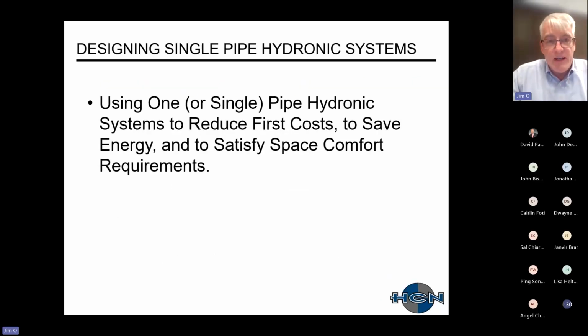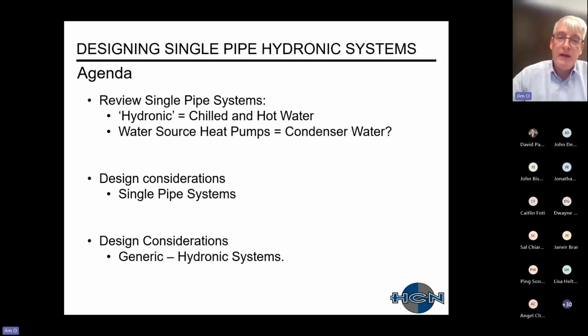So today the objective is just to go over single pipe hydronic systems and explain how they reduce first cost, how they save energy, and while doing that, they still will satisfy your space comfort requirements. Just three broad strokes of the agenda: first, I'll go over single pipe systems and the three main hydronic systems, which are chilled water, hot water, and then water source heat pumps. I put just the word condenser water because there's cooling tower water, and there's water for ground source systems, et cetera. But it is condenser water with the heat exchanger.